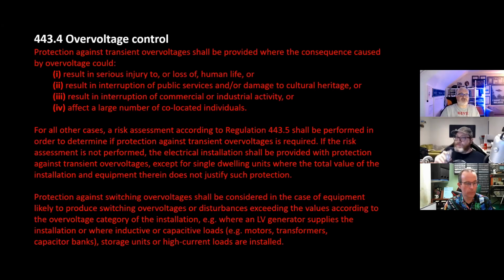It's overvoltage control. Protection against transient overvoltage shall be provided where the consequence caused by overvoltage could result in serious injury to or loss of human life, or result in interruption of public services and/or damage to cultural heritage, or result in interruption of commercial or industrial activities, or affect a large number of co-located individuals. Pretty much everybody there, let's be perfectly frank.